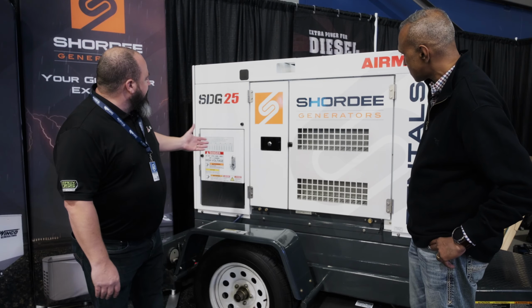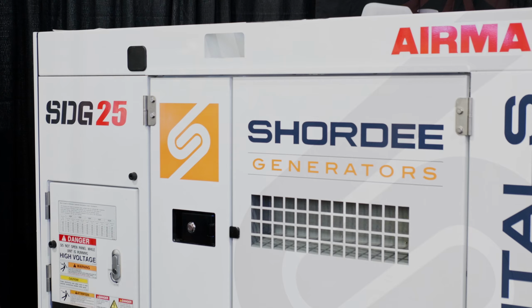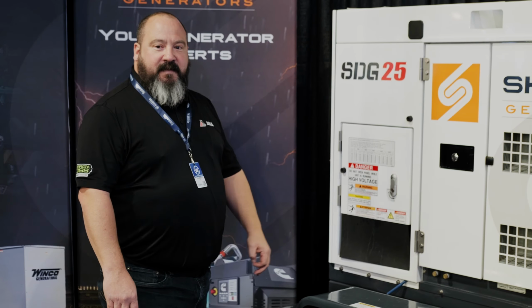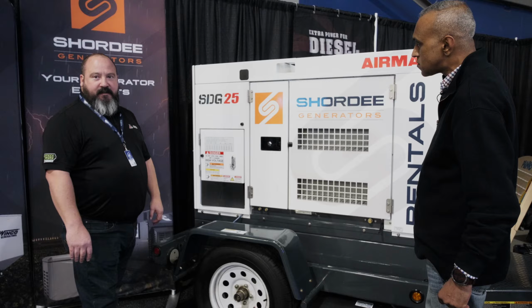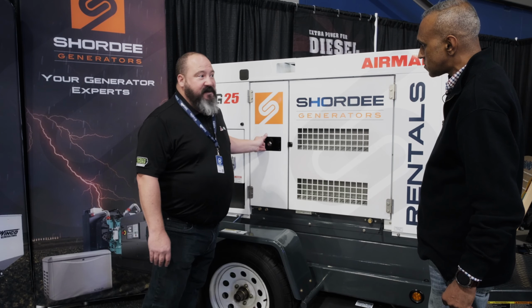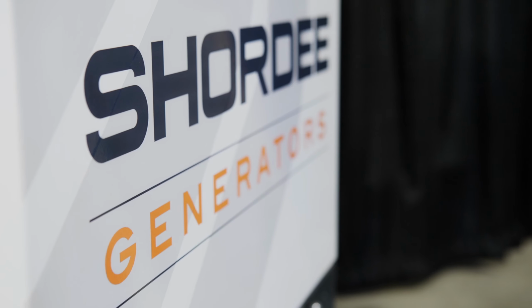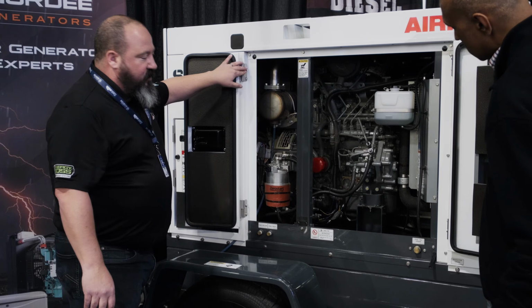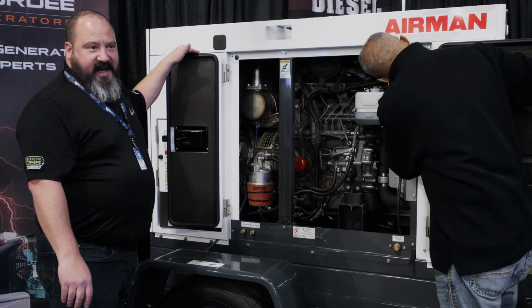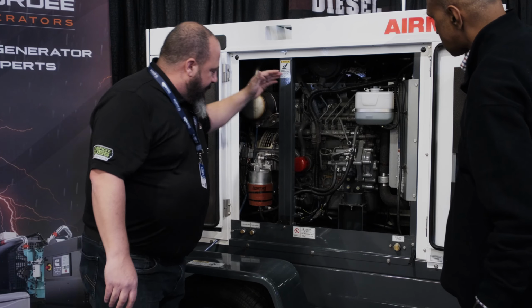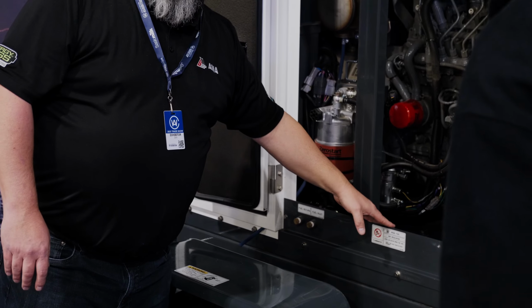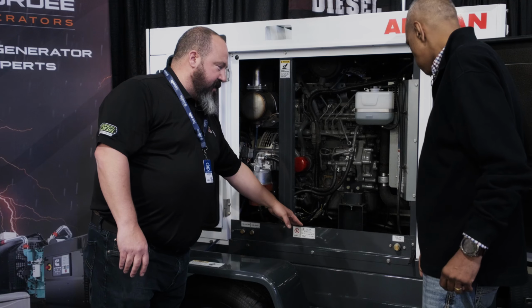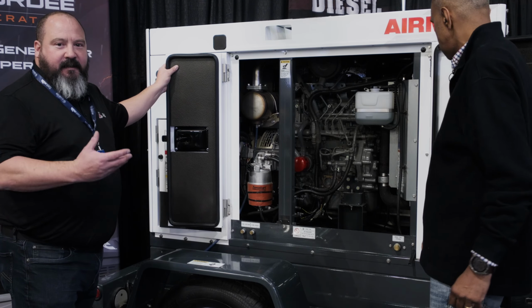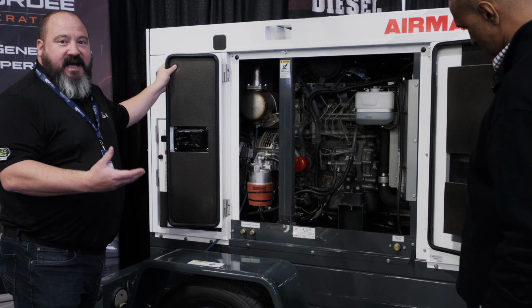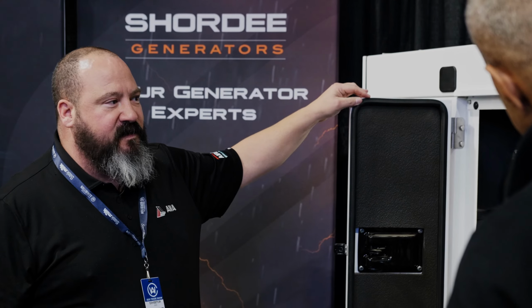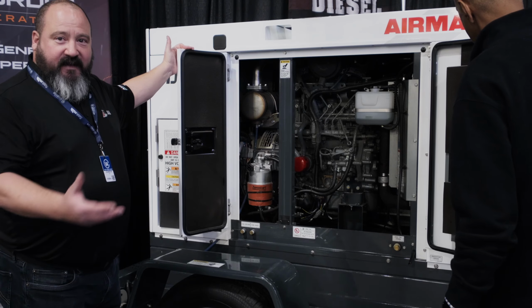Let's talk about this one in specific. This is our SDG25, giving us 25 kVA of prime power and 27 kVA of standby power. We're going to open it up and take a look at some of the features. First thing, when we open it up, we'll notice that we have stainless steel hardware on all of our removable doors for easy access to the equipment. A large 32-hour runtime at full load fuel tank built in. Sound attenuation, like I mentioned earlier, that gives us best in class sound rating. Automotive door seals so that it keeps the weather, the dust, the dirt, and everything out of the equipment.